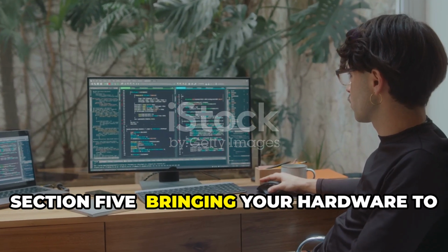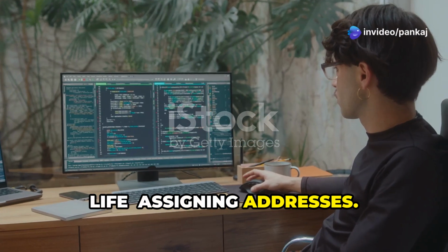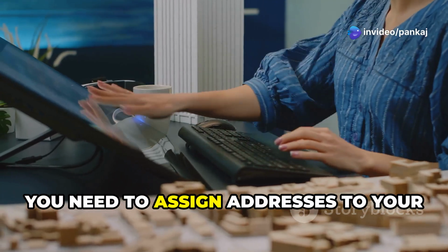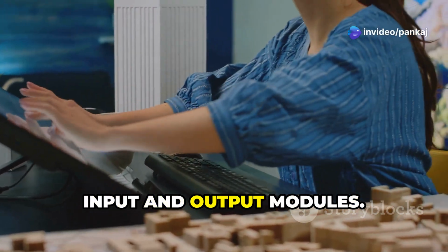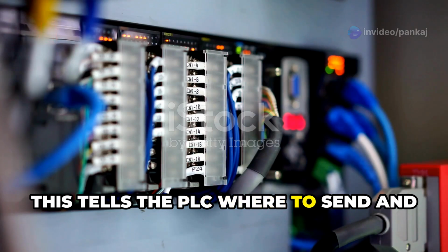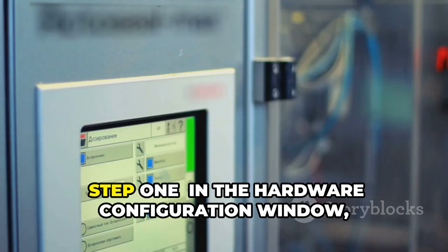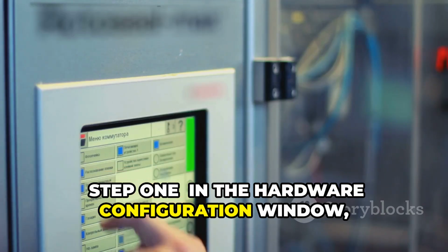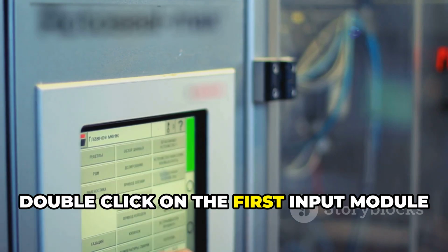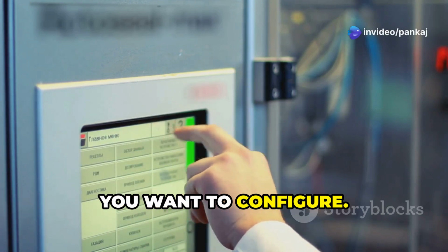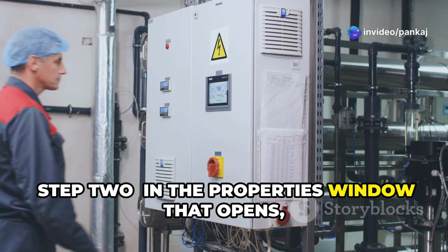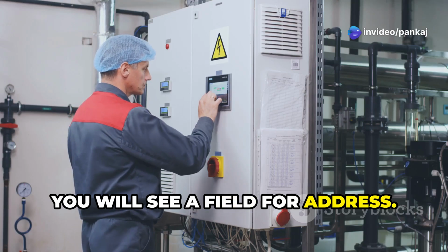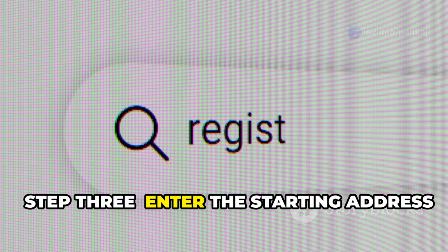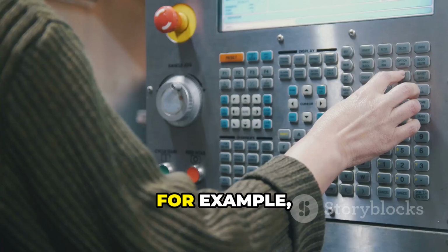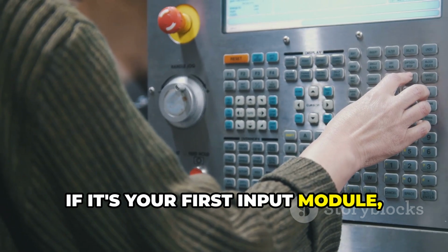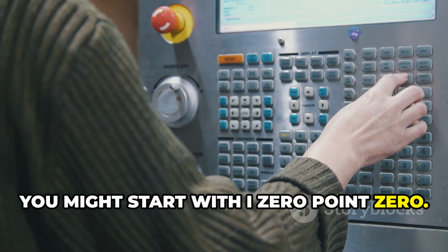Section 5. Bringing your hardware to life. Assigning addresses. With your hardware configured, you need to assign addresses to your input and output modules. This tells the PLC where to send and receive signals. Step 1. In the hardware configuration window, double-click on the first input module you want to configure. Step 2. In the Properties window that opens, you will see a field for address. Step 3. Enter the starting address for this module. For example, if it's your first input module, you might start with I0.0.